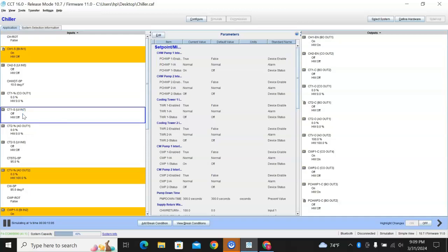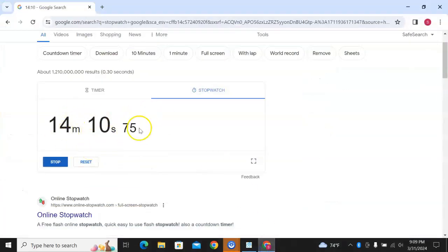Remember, it took 12 and a half minutes just to go over 100% over the top of the tower. So this is a hot day, obviously. Everything's heating up. We're gonna need those fans on to even start cooling down the water. All right, fan came on. 14 minutes.